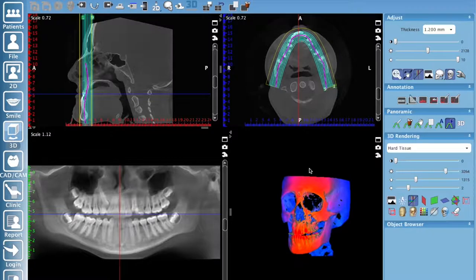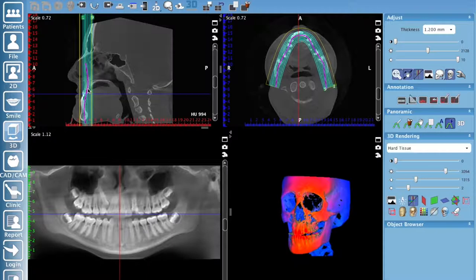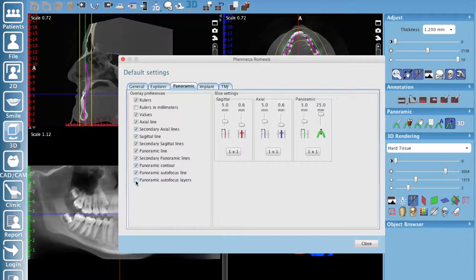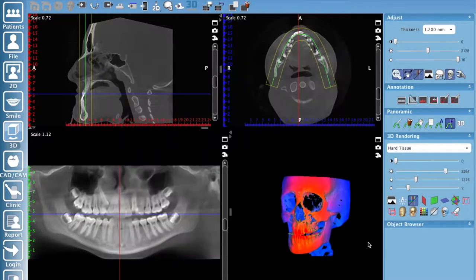You'll notice layer lines on the image. If they're impeding your view, go to the wrench icon — your default views — click it, make sure you're on the Panoramic tab, and you'll see options for Auto Focus, Layers, and Line. Click Layers to turn them off for a cleaner view, and click Auto Focus Line to remove that as well. That's how I set up my default settings in Romexis for the panoramic sub-module.